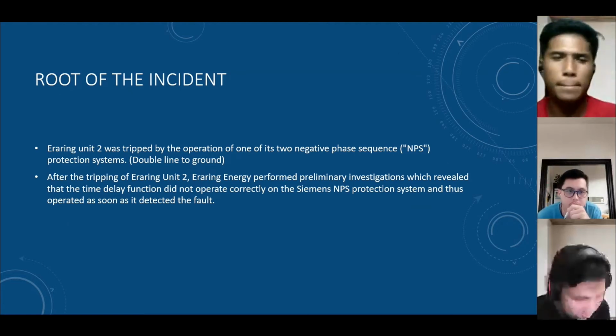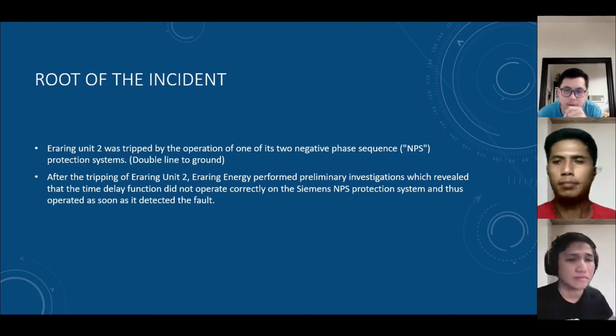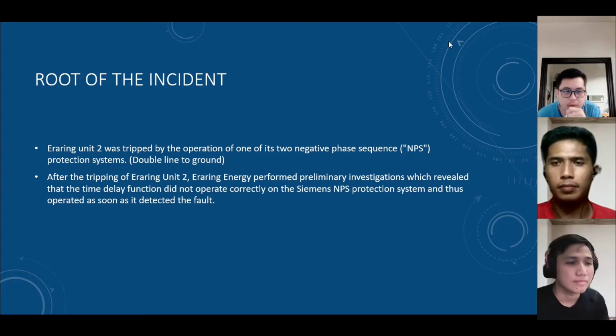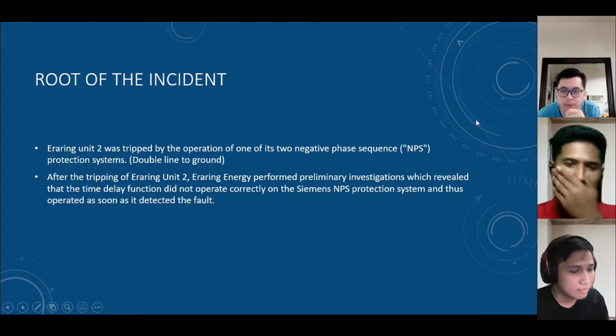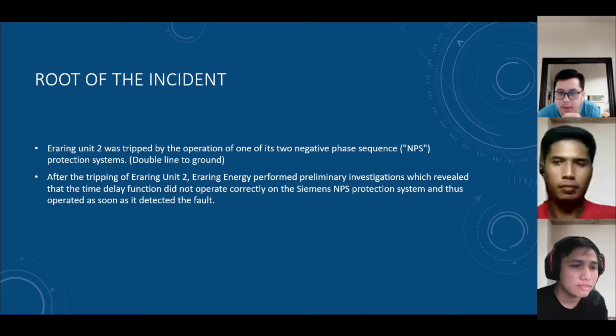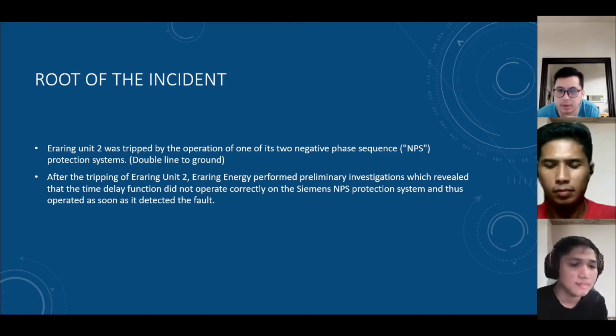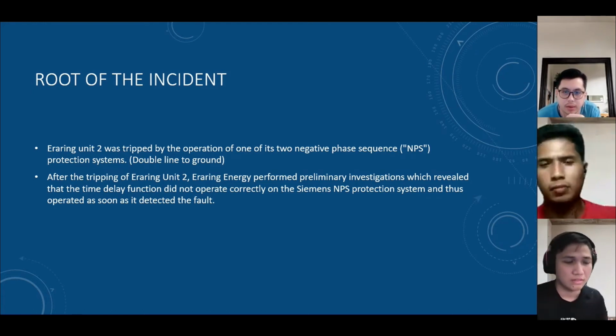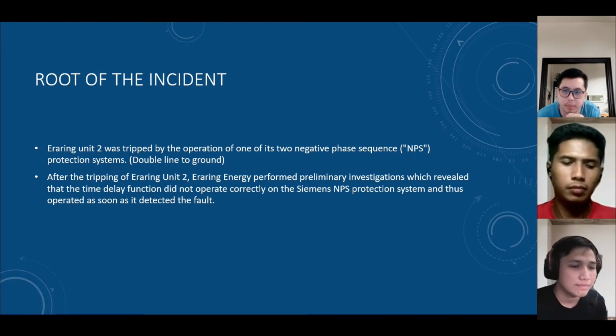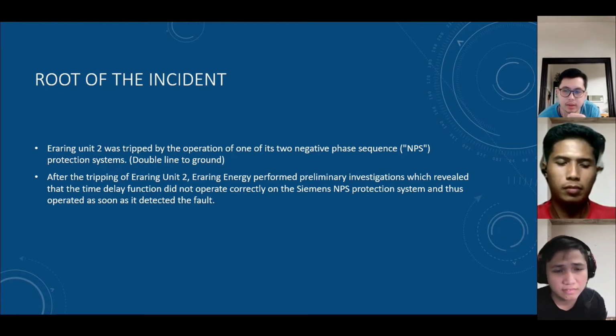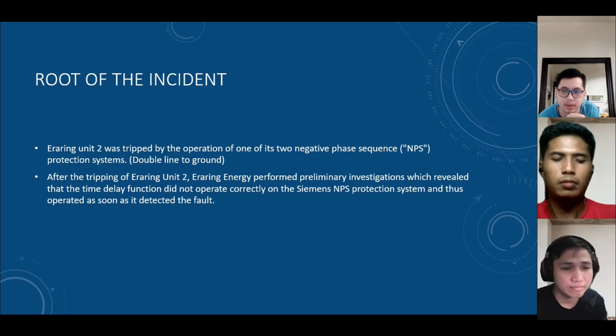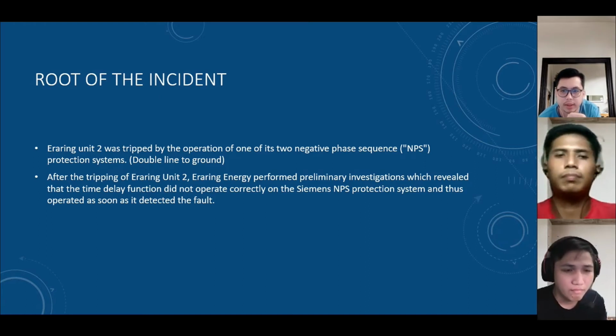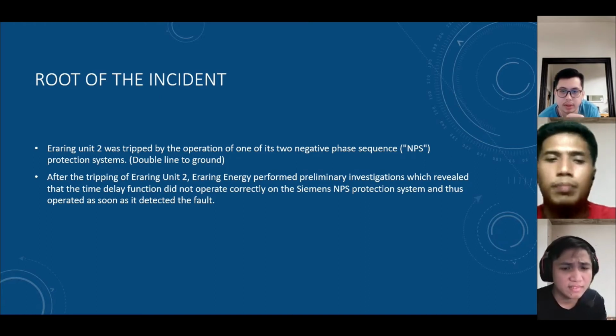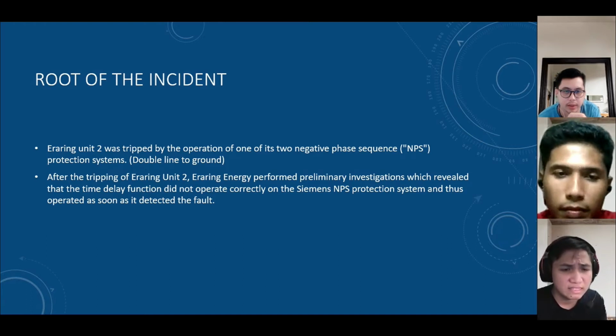Next, we will talk about the root cause and the consequences of the incident. The unit was tripped because of negative phase sequence protection operating, which is more consistent with a double line to ground fault. From the preliminary investigation, it was also said that the time delay function did not operate correctly on the Siemens negative phase sequence protection system, and thus the operation was detected as a fault. Next.